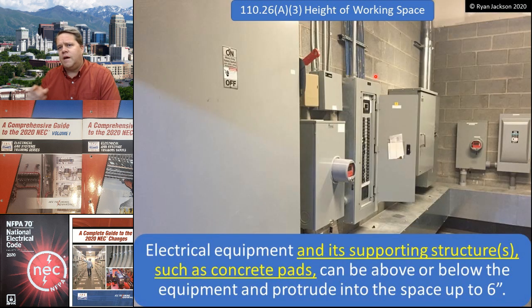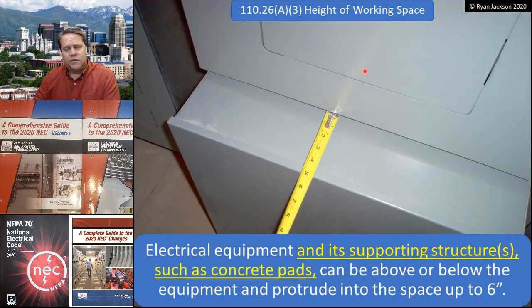Now, do me a favor and let's read this without the code change first. Electrical equipment can be above or below the equipment and protrude into the working space up to 6 inches. This is the reason that installing a wireway like this underneath the equipment is permitted. I can put electrical stuff below or above the other electrical equipment as long as it doesn't stick out more than 6 inches. And that makes sense.